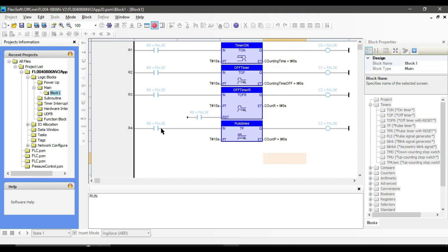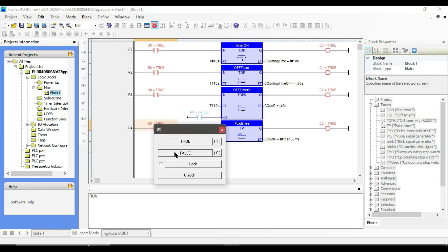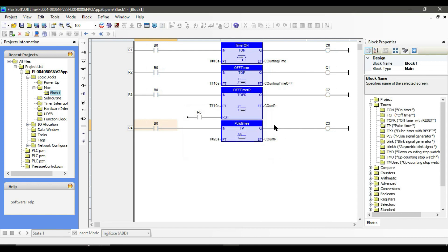As soon as you turn on the input, the output will also turn on and the elapsed time starts counting. When the elapsed time reaches the preset time — which is the length of our pulse — the output turns off and the elapsed time stays at the pulse time. When we turn off the input the elapsed time resets to 0. If we turn on the input again, the output turns on immediately and the elapsed time starts counting. Even if we turn off the input, the elapsed time will still keep counting, because this is used for generating a pulse of a specific length. No matter how many times you turn on and off the input, no change will happen to the output before the elapsed time reaches the preset time.